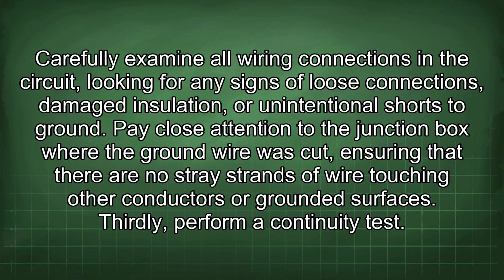Carefully examine all wiring connections in the circuit, looking for any signs of loose connections, damaged insulation, or unintentional shorts to ground. Pay close attention to the junction box where the ground wire was cut, ensuring that there are no stray strands of wire touching other conductors or grounded surfaces.